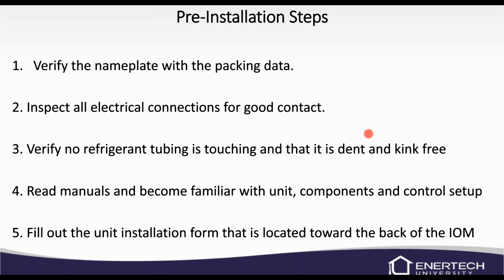So definitely always fill out the startup sheet, and not that Enertech necessarily needs it, but if you want to send it to us, we'll take a look at it and file it away. But definitely keep it with the unit. Keep the IOM with the unit as well. Now, speaking of the IOM, I would not give that to the homeowner. The reason I wouldn't is that the IOM is the install operating manual. So there are things in there that you're supposed to do when you install a unit.